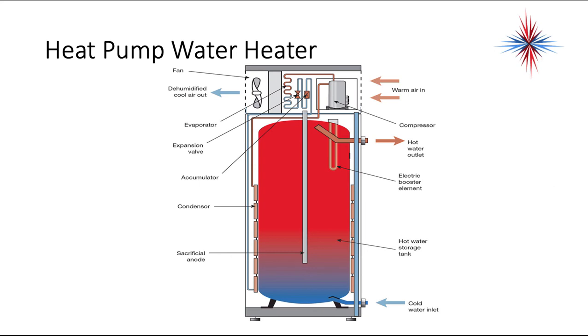You have a refrigeration system, and your warm air comes in and passes across the compressor just to help cool the compressor a little bit. It comes through an evaporator coil, which is picking up heat, and then comes back to the compressor. Now the discharge gas from the compressor goes to a condenser that is mounted alongside the water heater in this case. There are some variations of this also, where the water is circulated through a tube-in-tube heat exchanger as well. Both are available, so just be aware when you look at these.